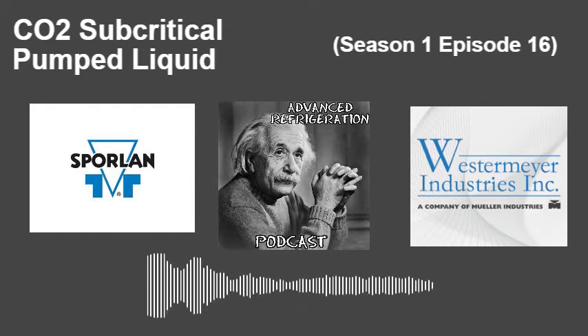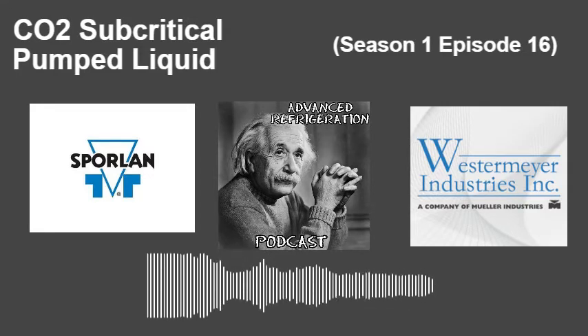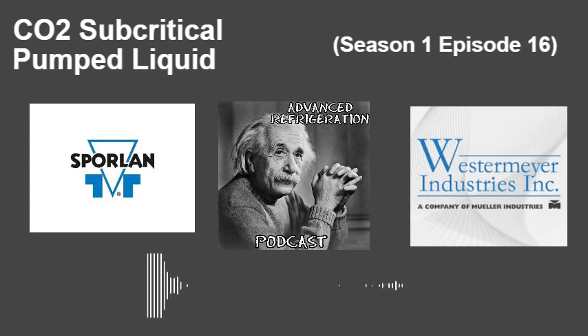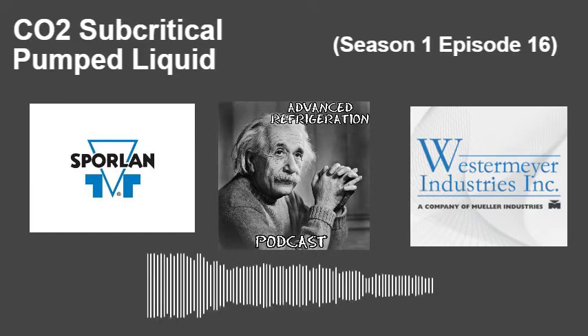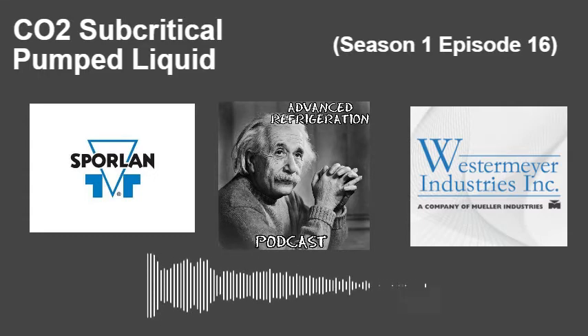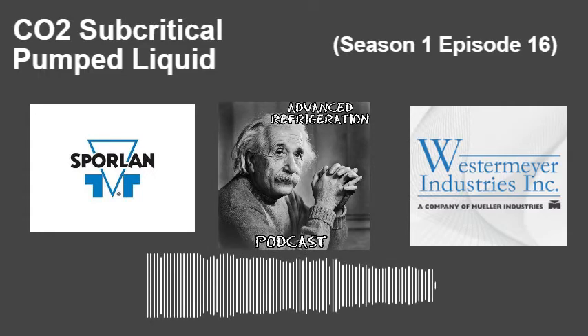So, now I kind of want to go over the HFC part of it. Sure. So what we're going to have is a standard rack. You hope. There's some older versions of this with single units. We have 2 stores like that. They are absolute disasters. They're single unit CO2 systems, where instead of a rack, they have 4 individual glycol cooled single systems, and they're doing the CO2. Yeah, it's a horrible system. It has nothing but problems, and it's one of the original Walmarts where they tried this.